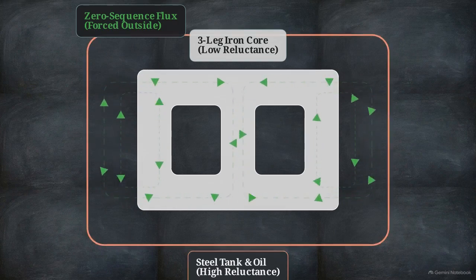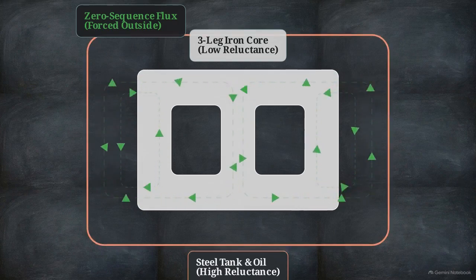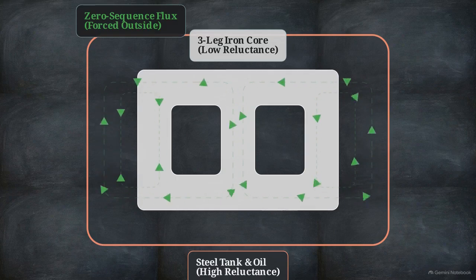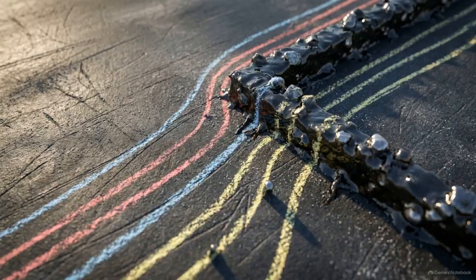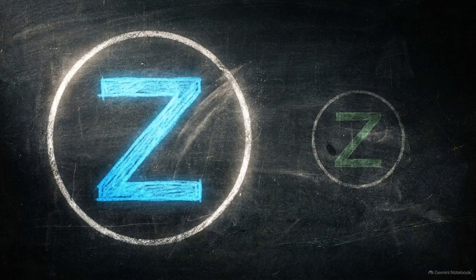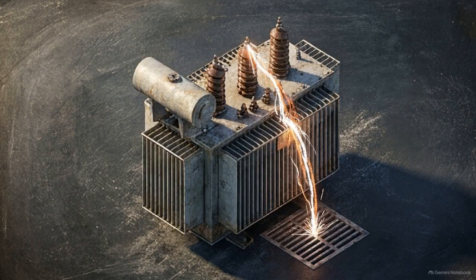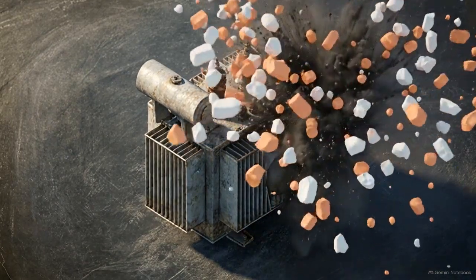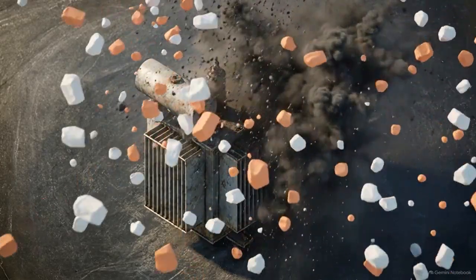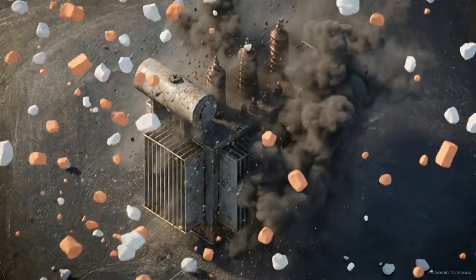To complete its circuit, it must force its way through the high-reluctance steel tank or the surrounding insulating oil and air. Because magnetic reluctance heavily impedes the flow of flux, this specific physical layout results in a zero-sequence impedance that is significantly lower than the transformer's positive sequence impedance. Due to this low impedance path, a single phase-to-ground fault on the secondary terminals of a core transformer will often generate a higher, more destructive fault current than a complete three-phase short circuit at the exact same location.